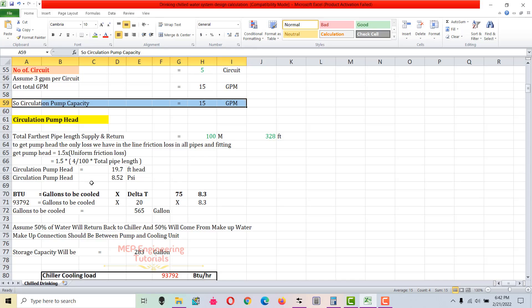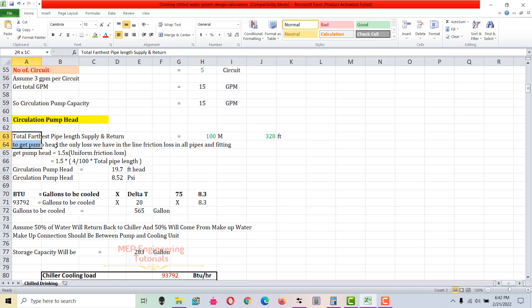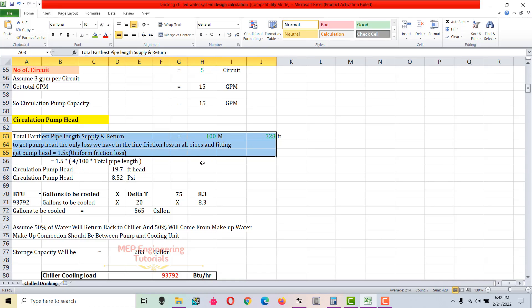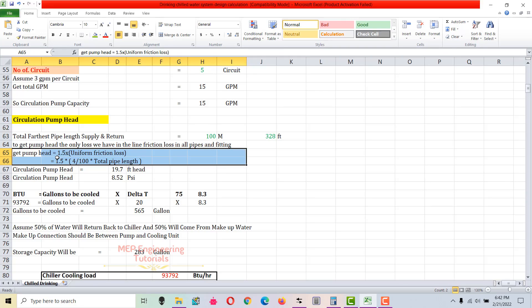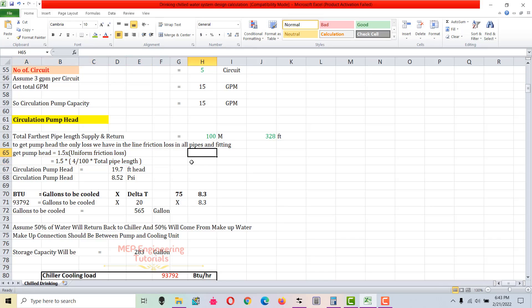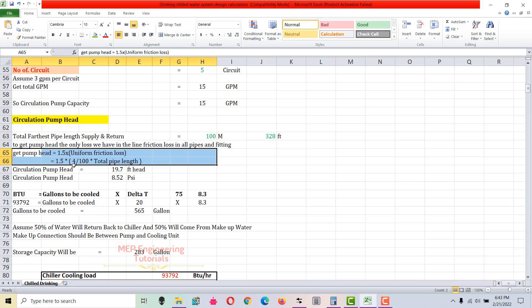Now I calculate the circulation pump head. For the head calculation, we check the furthest pipe length for supply and return. There are two types of losses: straight pipe length loss, and fittings and component losses. I assume 50% of the straight pipe losses account for fittings and components, so I multiply by 1.5. The formula is: head = 1.5 × uniform friction head loss × total pipe length. The uniform friction loss I'm using is 4 feet per 100 feet of pipe.